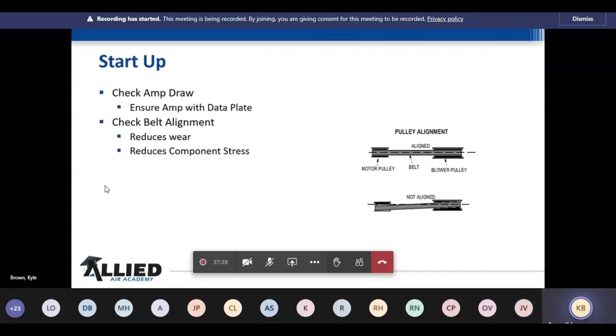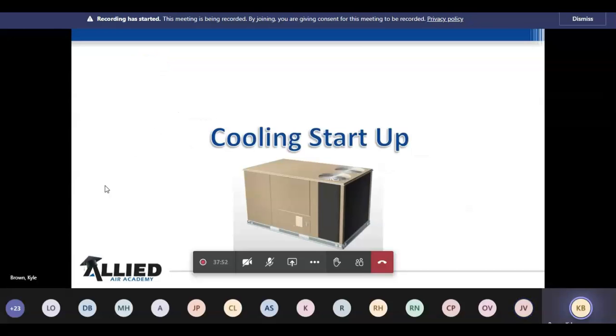So belt alignment, if it's out of line, your belt's going to wear out quicker, but it can also cause a lot more vibration in the unit. You can check the amp draw as well too. It's going to make your amp draw go up. But we'll talk about that in a few minutes as well.